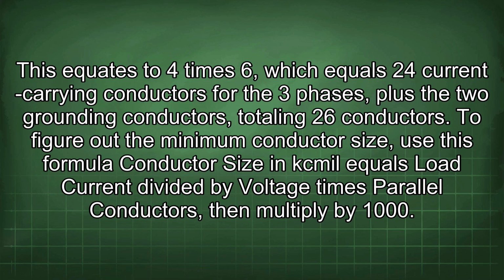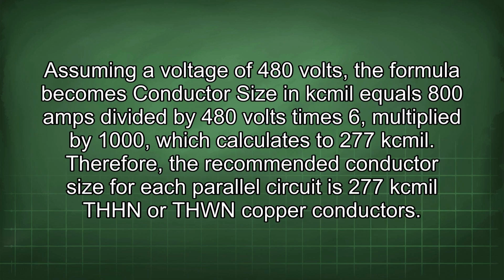To figure out the minimum conductor size, use this formula: conductor size in kcmil equals load current divided by voltage times parallel conductors, then multiply it by 1000. Assuming a voltage of 480 volts, the formula becomes conductor size in kcmil equals 800 amps divided by 480 volts times 6, multiplied by 1000, which calculates to 277 kcmil. Therefore, the recommended conductor size for each parallel circuit is 277 kcmil THHN or THWN copper conductors.